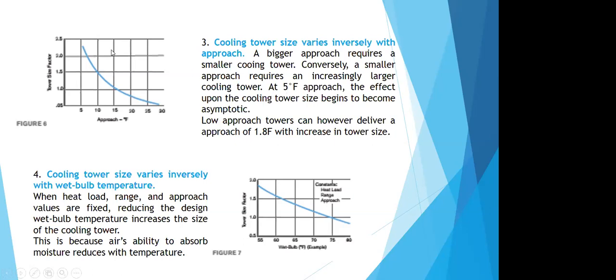So at 5 degree approach or below, the effect on the cooling tower size becomes asymptotic. So it's not linear, it becomes exponential. If you reduce the approach, it becomes tougher to achieve the conditions. You need a larger surface area to achieve the same cooling water temperature. However, low approach cooling towers can deliver an approach of 1 degree centigrade or 1.8 degree Fahrenheit with an increase in tower size. How we do that is by increasing the tower size by almost 2 times the tower size at the normal approach of say 7 degree Fahrenheit.